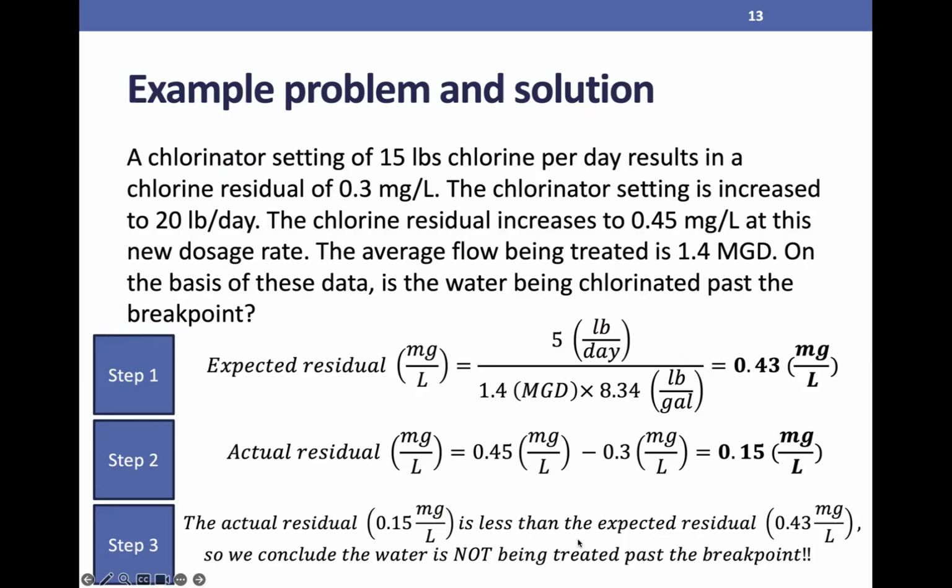Finally, we compare the actual and expected residual. We see that the actual residual of 0.15 milligrams per liter is less than the expected residual of 0.43 milligrams per liter, and so we conclude the water is not being treated past the breakpoint.